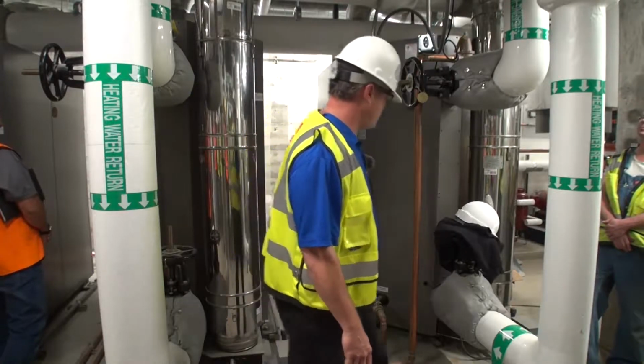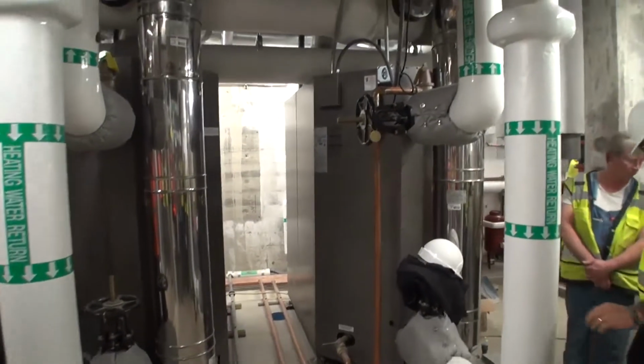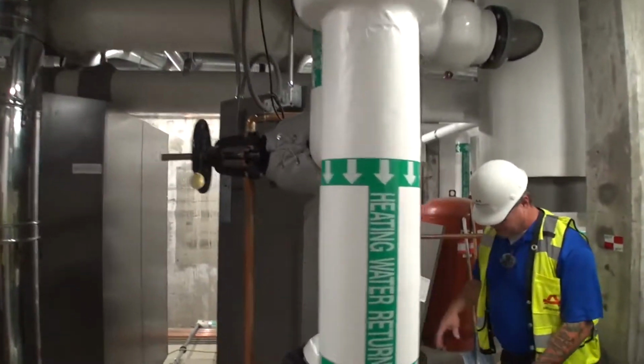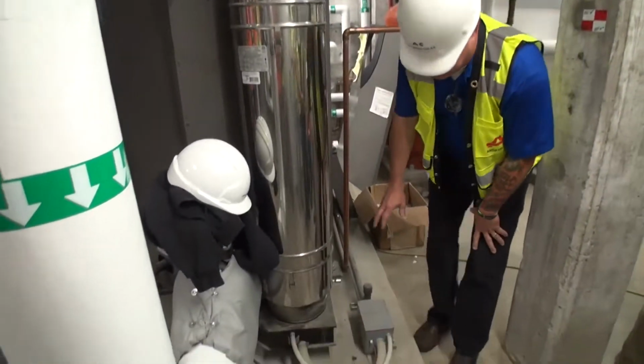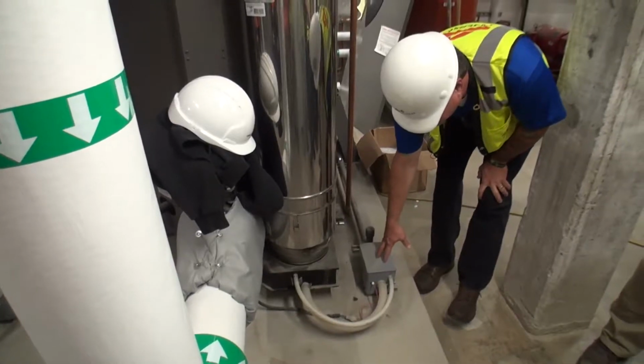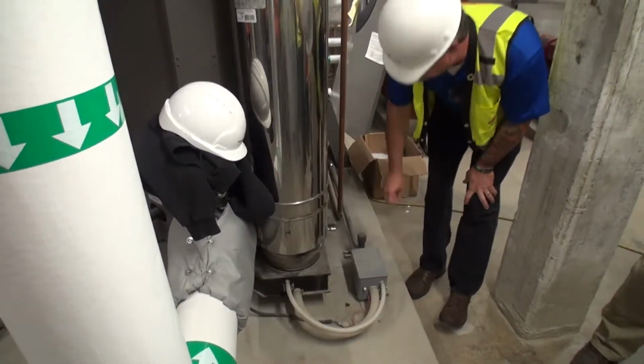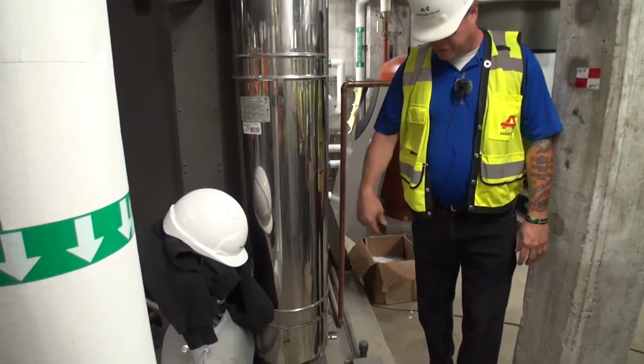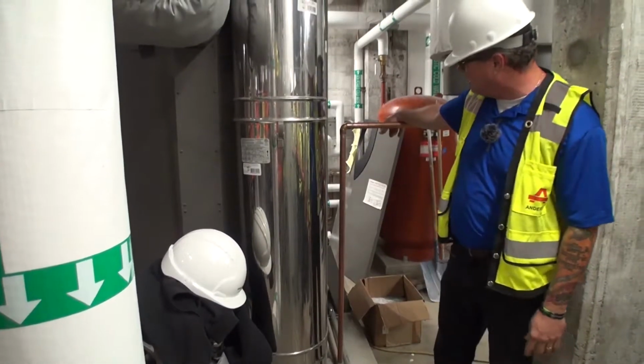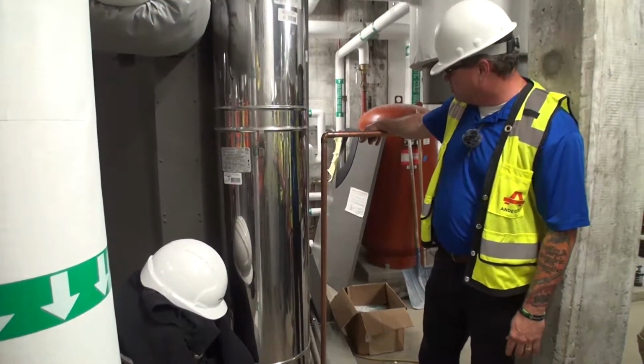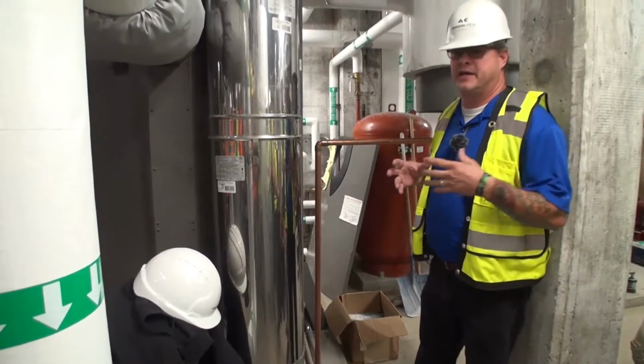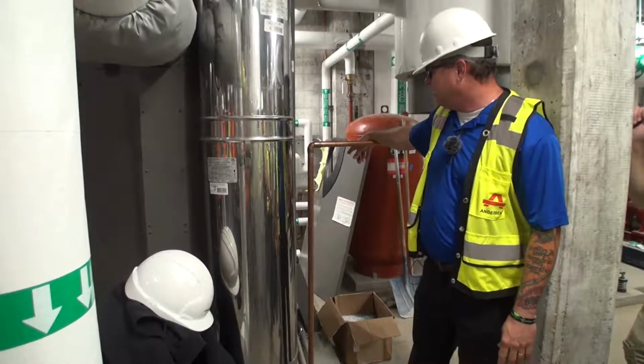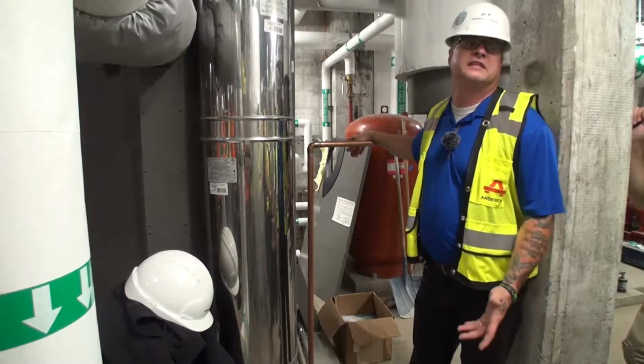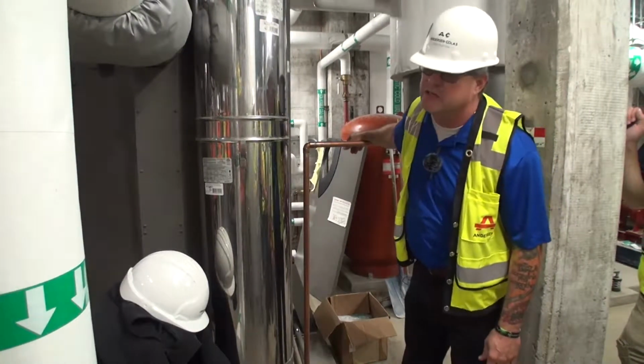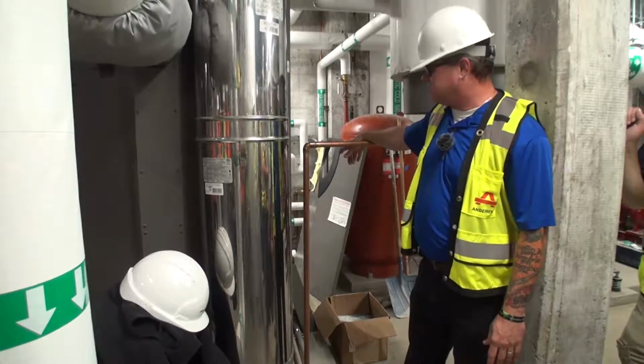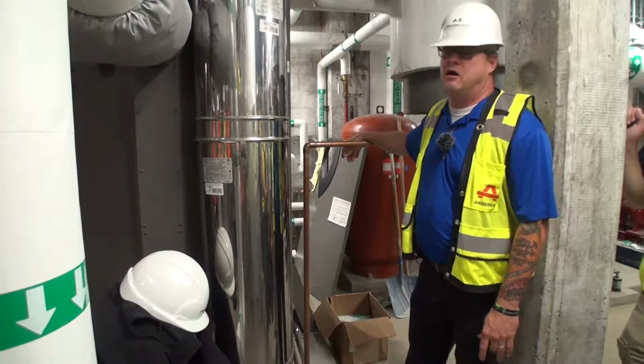Basically, what we need to look at here, on the back side of the boiler, the main thing is our neutralizer, the condensate neutralizer. It comes down through the venting, comes back, and then goes to a neutralizer that has pellets in it that neutralizes the water. That probably needs to be looked at about every 6 months to a year. What do you think, Sheldon? So about every 6 months to a year that needs to be looked at or tested.